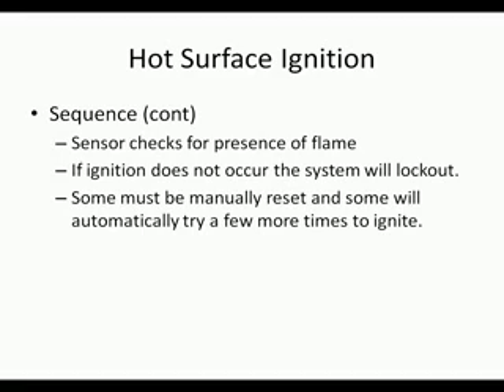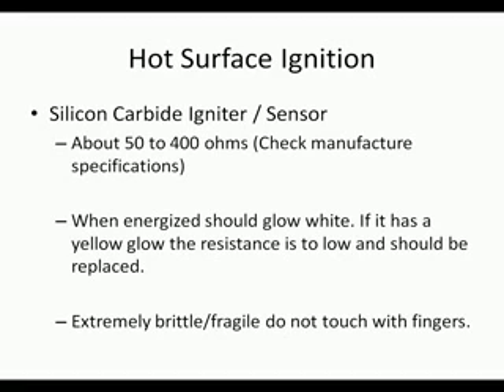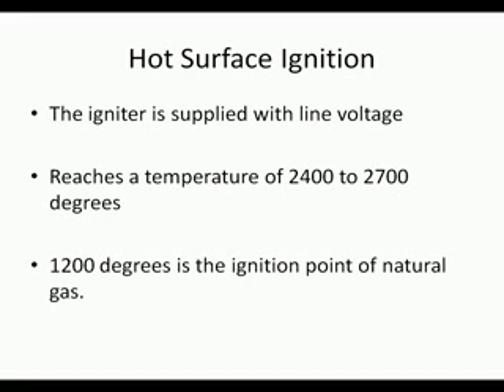When the thermostat calls for heat, the igniter element is powered with 120 volts. The hot surface ignition is energized for 45 to 60 seconds. Then the main gas valve opens. When the main burner lights, a trial for ignition occurs. This trial lasts 7 to 15 seconds. During the trial for ignition, the igniter switches from a heater to a sensor. The sensor checks for the presence of a flame. If the ignition does not occur, the system will lock out. Some ignition systems must be manually reset, and some will automatically try a few more times to ignite.